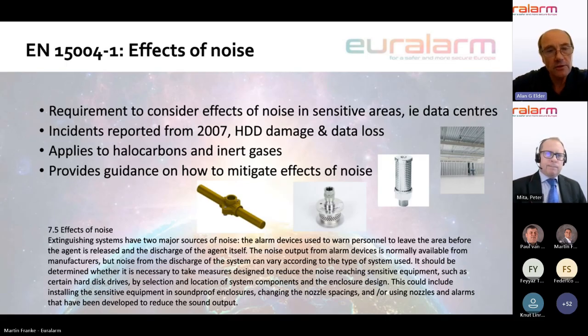And so what the standard does is in that last sentence. It says this could include installing the sensitive equipment in soundproof enclosures, changing the nozzle spacings, and or using nozzles and alarms that have been developed to reduce the sound output. I think the most common method here of mitigating against this noise in respect to the discharge is to include acoustic nozzles, and there's a number of those on the market from the various OEMs, and there's some pictures of some of the ones that you may have seen in practice. So different configurations, different technologies there, but all designed to reduce the sound power from the discharge nozzle itself.